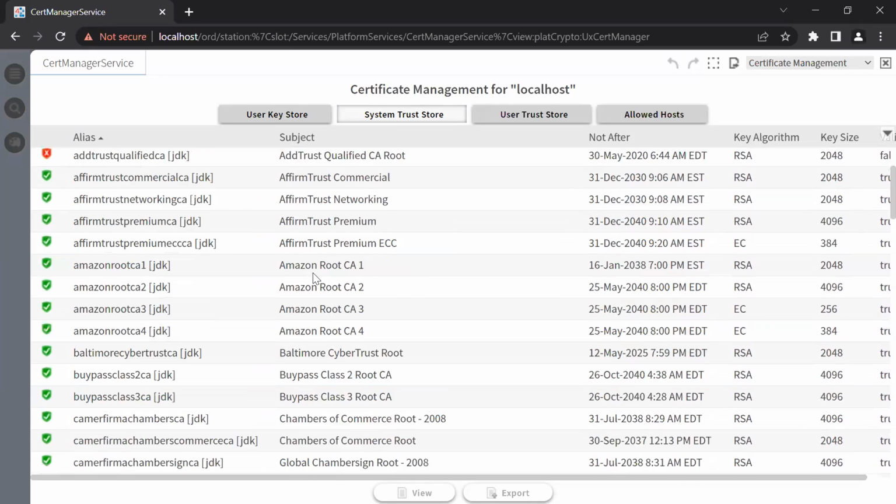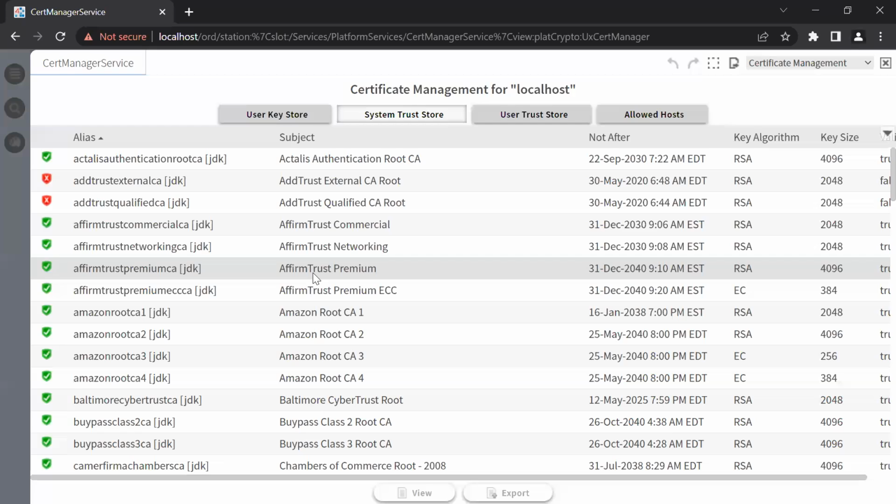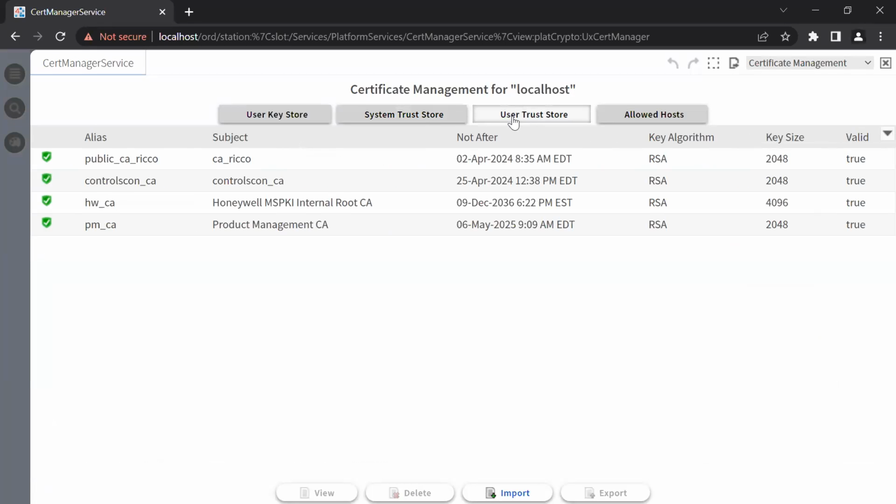And so we explained last week that you can obviously pay for this service. There's a convenience in that you don't need to add the authority to the trust store, but you don't have to use them. You simply could add to the trust store yourself. And in Niagara, we like to separate these two by showing off the user trust store, system implying pre-populated and locked out, user implying something you can add to. So in this case, I already have some CAs just sitting in here.